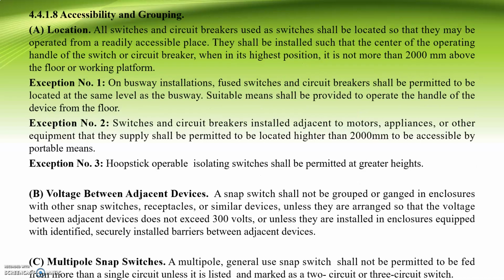Chapter 4.4.1.8, accessibility and grouping. A, location. All switches and service circuit breakers used as switches shall be located so that they may be operated from a readily accessible place. They shall be installed such that the center of the operating handle of the switch or circuit breaker, when in the highest position, is not more than 2000 mm above the floor or working platform. Exception number 1: on busway installations, fuse switches and circuit breakers shall be permitted to be located at the same level as the busway.